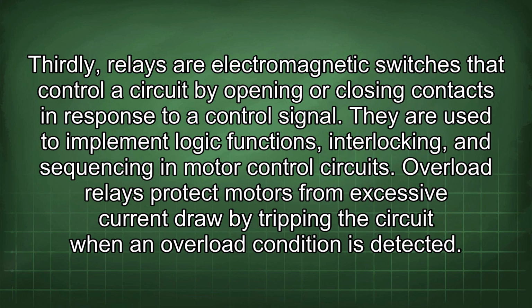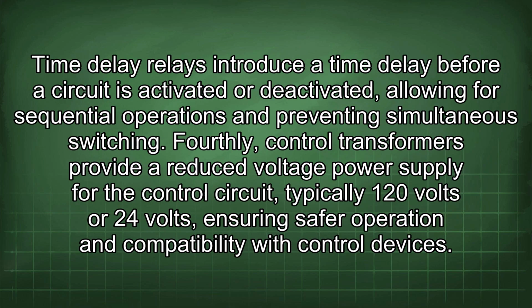Thirdly, relays are electromagnetic switches that control a circuit by opening or closing contacts in response to a control signal. They are used to implement logic functions, interlocking, and sequencing in motor control circuits. Overload relays protect motors from excessive current draw by tripping the circuit when an overload condition is detected. Time delay relays introduce a time delay before a circuit is activated or deactivated, allowing for sequential operations and preventing simultaneous switching.